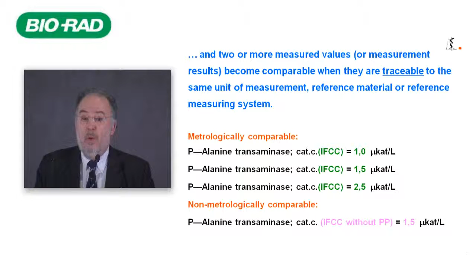So, two or more measurement values or measurement results become comparable when they are traceable to the same unit of measurement, reference material or reference measuring system. In the example, the alanine aminotransferase or alanine transaminase measurement of catalytic concentration in plasma, in the 3 cases the results are comparable because all 3 have traceability to the IFCC reference measurement procedure. But in the other case, because there is a modification in the reference procedure, we cannot say that this measured value is traceable with the others.